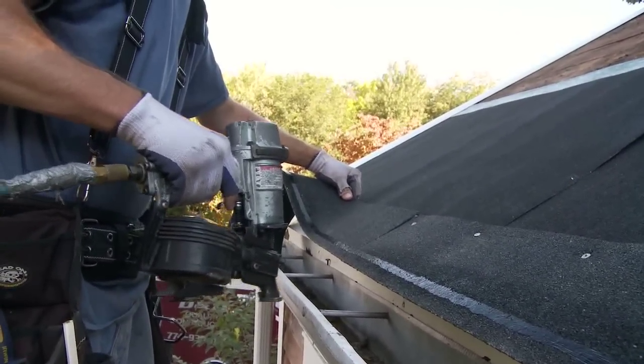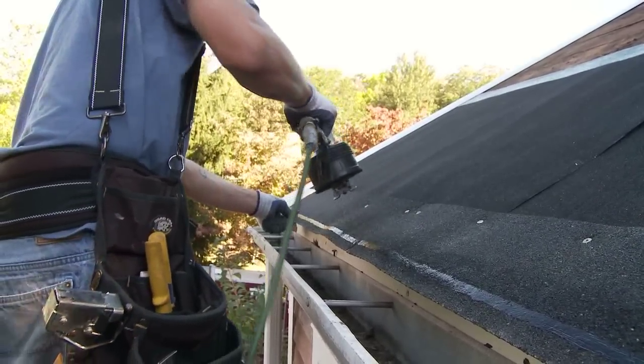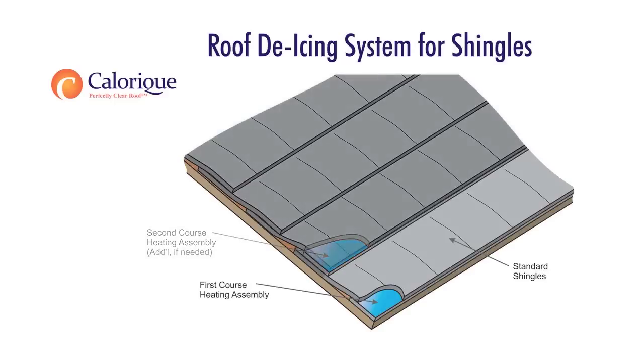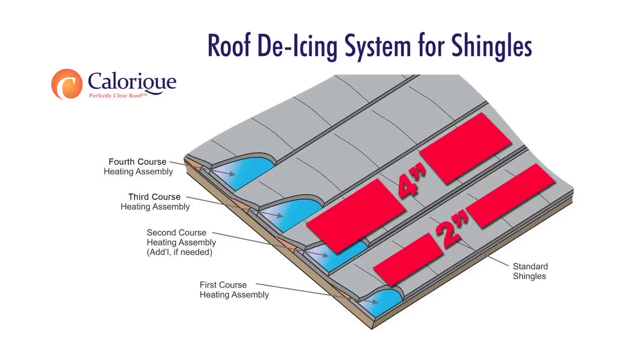The roofer then measures the area where the roof de-icing system is to be installed, usually somewhere between 6 inches from the outer edge of the roof to within 6 inches of the valley. There are two components of the Calorique Roof De-Icing System: the starter heating course and the roof deck heating course. The starter heating course is only used on the leading or starting edge of the roof deck and uses a 2-inch heating element. The main roof deck heating course uses a 4-inch heating element and can be run in multiple courses as needed for ice dam prevention.